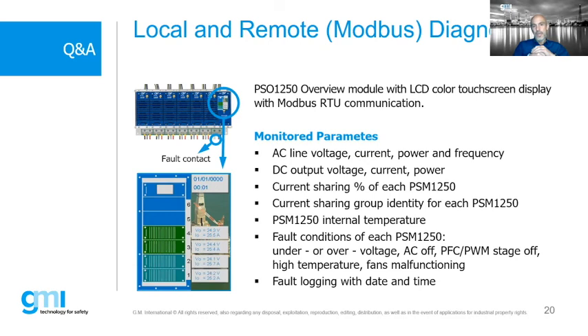can also be reported to the system, because there are two ways: you can have a common alarm contact you can transmit, and also there is the Modbus RTU, the field bus output. Through the field bus output, you can discriminate exactly what fault happens on your power supply. That is the real value. And all systems basically support Modbus RTU communication.